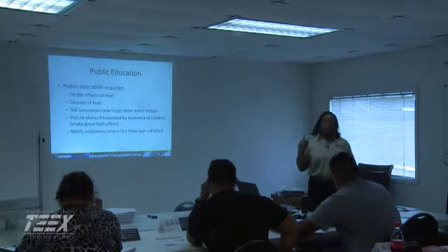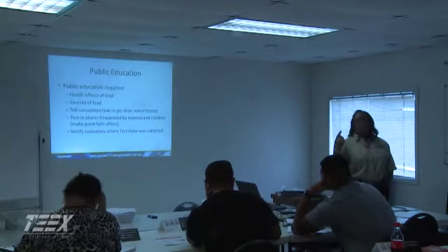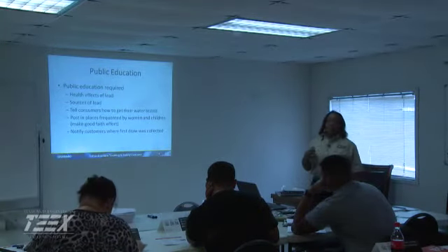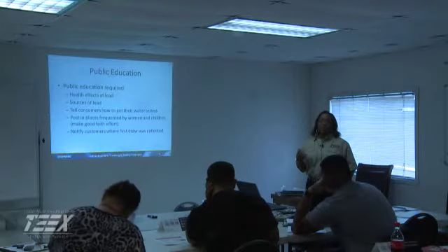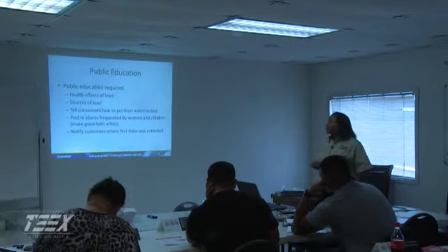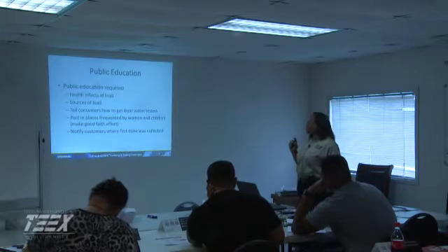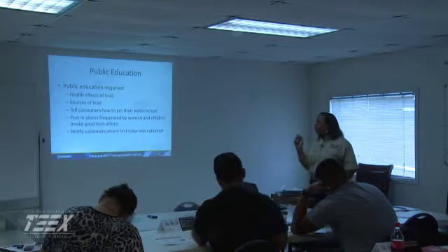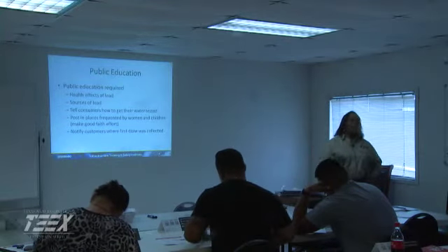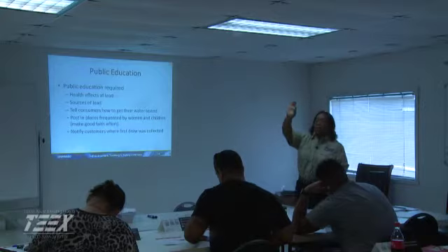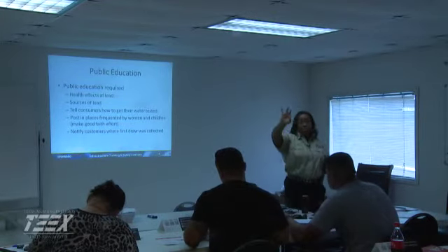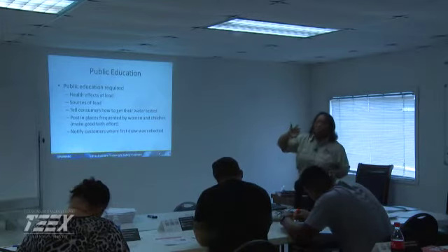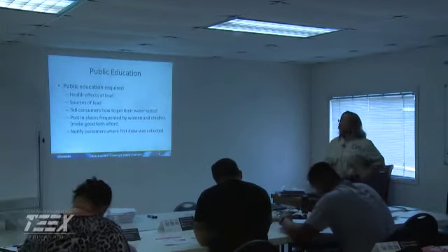Within your public education that's required, you want them to know what are the effects of exposure to lead and copper, what are the sources of lead and copper, and primarily we've established the source would be your plumbing. Tell the consumer how to get their water tested, and you want to make sure you're posting this in places that are frequented by women and children. You have to certify that you've made at least a good faith effort, at least 3 attempts. In other words, 3 places you're going to post this, or 3 different medias that you're going to utilize to get the word out.